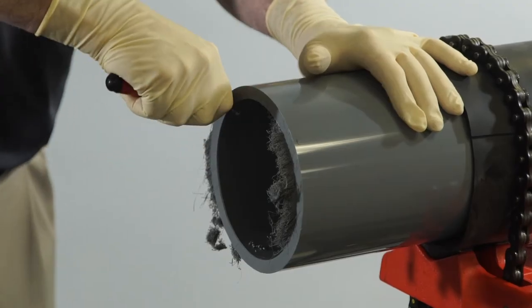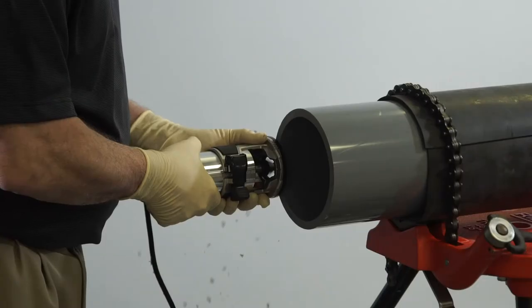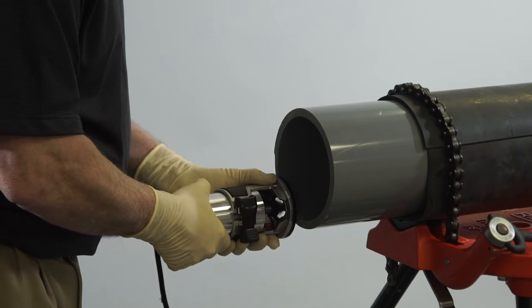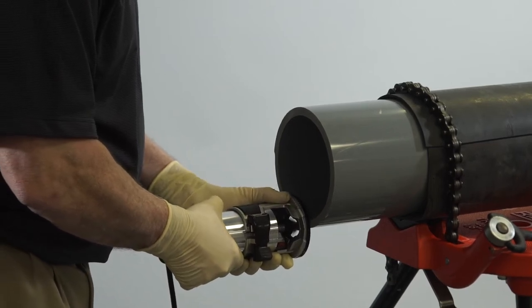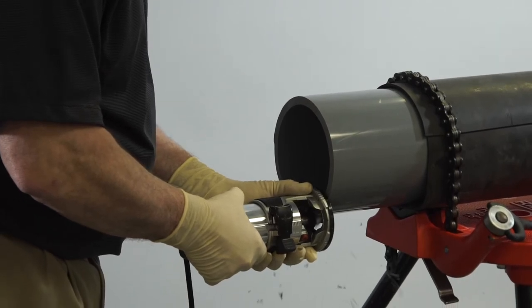Remove inside diameter burrs or raised beads with an internal deburring tool or knife. Remove any burrs or raised beads on the outside diameter of the pipe. Burrs can create channels into pre-softened surfaces or can create gaps across the mating surfaces.